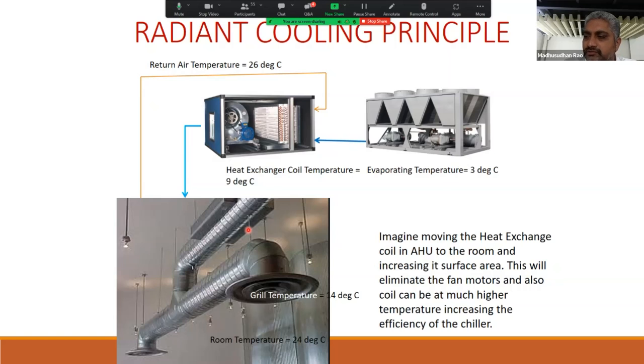One thing we need to appreciate here is that radiant cooling is a low side technology. So if you ask what is the COP of radiant cooling, it has no COP. What it is doing in essence is replacing the AHU and ducting. It is not replacing the chiller. It still needs that, but it is primarily replacing the AHU and ducting. So it's a low side technology, or a cooling distribution technology, not a cooling generation technology.